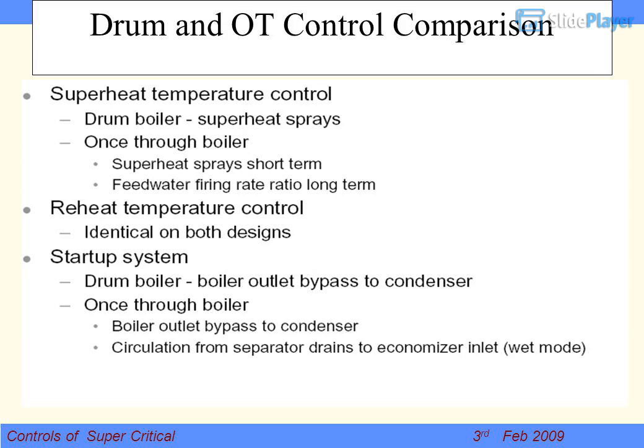Drum and OTU control comparison continued. Superheater temperature control: why is it required? In drum type there are two methods — burner tilt and superheater spray. In OTU, superheater spray is used for short duration only; feed water and firing ratio is used for long-term temperature control. Reheater temperature control is the same for both drum and once-through types.